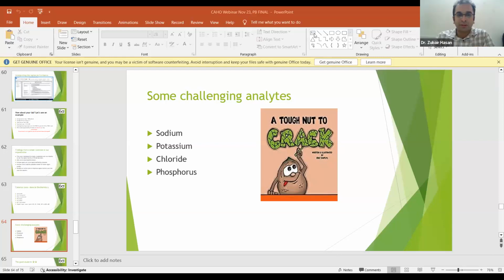Next question. If some parameters have total allowable error in both the biological variation database and CLIA as well, which should be followed for total error acceptance? In the Stockholm hierarchy, biological variation is rated above CLIA. So from that logic, you can go with biological variation. It is definitely more accurate and slightly more stringent than CLIA, which is not too tight in that sense. In that case, I would say biological variation, because we have a scientific document which puts biological variation immediately after medical decision limits. Yes.